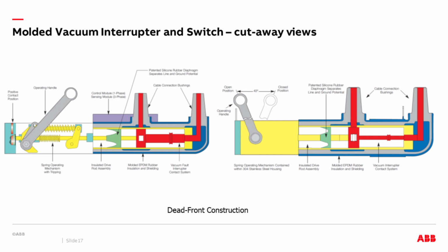And here's a cutaway of what the switch and the interrupter look like. You can see the red parts show the current path through the bushings. The bushings are standard IEEE 386 interfaces, so you can plug 600 amp T-bodies directly onto both sides, with the bottle, the vacuum switch, in between inside the rubber. There's a pole that operates this, which is enabled by the handle or by a spring mechanism and a trip coil on the left for the interrupter. There's a small purple block in the center of the left picture, which represents the current transformer. So the current transformer is monitoring the current through that bushing. And then depending on how the customer programs its trip settings, it'll initiate a trip when that threshold is exceeded.